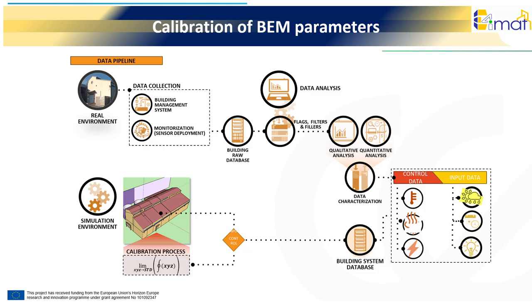The second pipeline is dedicated to data analysis for the building. The key aspect of this pipeline lies in the data management plan and its application. First, it is here that the project requirements define the grain of resolution of the data obtained, for example, 10 or 15-minute data stream, hourly data, or other.